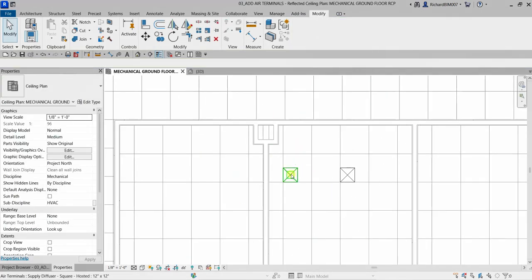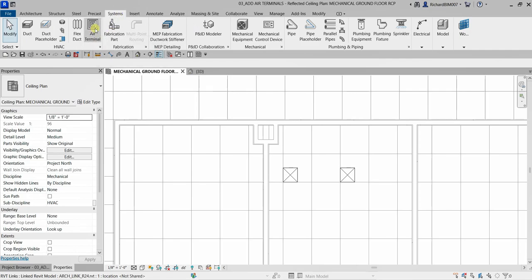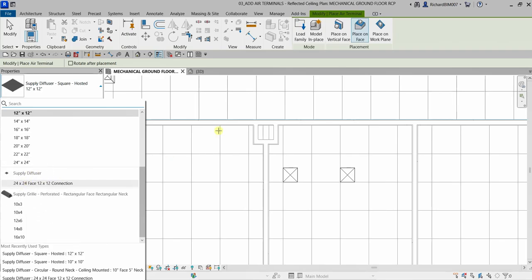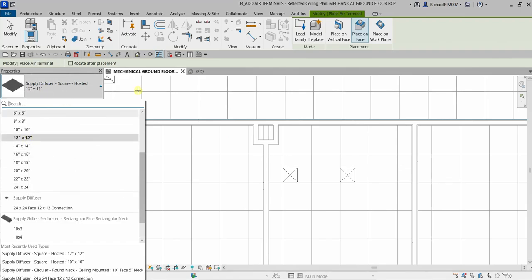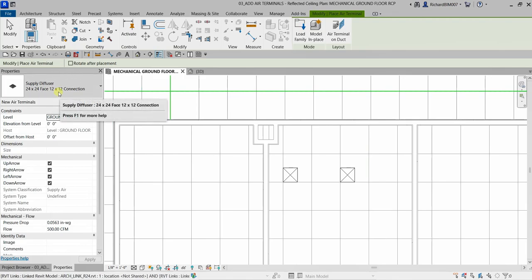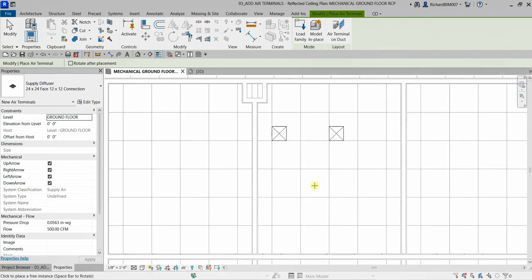After viewing the two air terminals in 3D, I'm going to select the Air Terminal tool again and change the type. This time I'll use a non-hosted family - you can see the name is simply 'Supply Diffuser' without 'Hosted.' Notice the three placement options disappear when you select this non-hosted family. The reason you can't see it in the ceiling plan is because by default its height is zero, starting from ground floor level, so you need to specify the height.